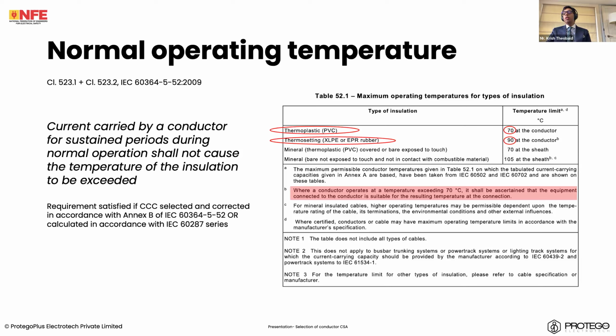But unless we know that all the connected equipment, accessories, terminations, all connected electrical equipment, can also withstand this temperature that exceeds 70 degrees, for example, 90 degrees, we cannot actually use a 90 degree current carrying capacity. We have to derate or use a 70 degree capacity, even though we're using a thermosetting cable. It's very important to keep that in mind.